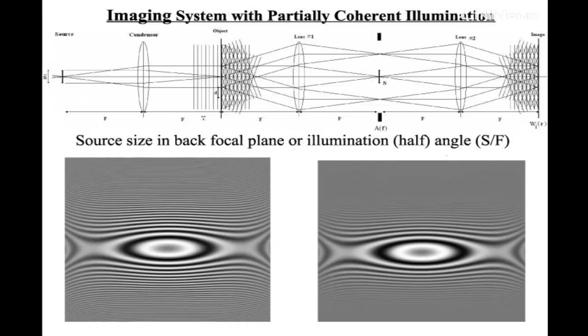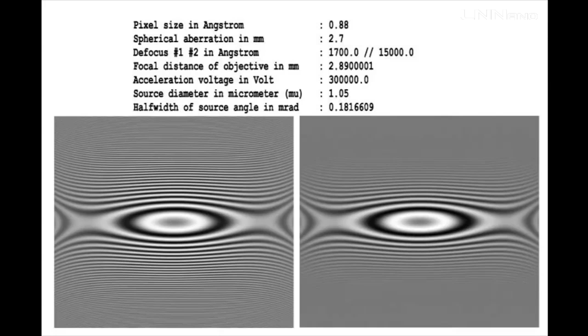Here, same picture again, just some of the parameters. The highest resolution is 0.8 angstroms or 0.9 angstroms here. And spherical aberration, these values come from a Titan. 1700 angstroms resolution, defocus in this direction, 15,000 here are the real values. And the calibrated focal distance of the objective lens, 300 kilovolts. And here is the millirad, so 0.18 millirad beam convergence.